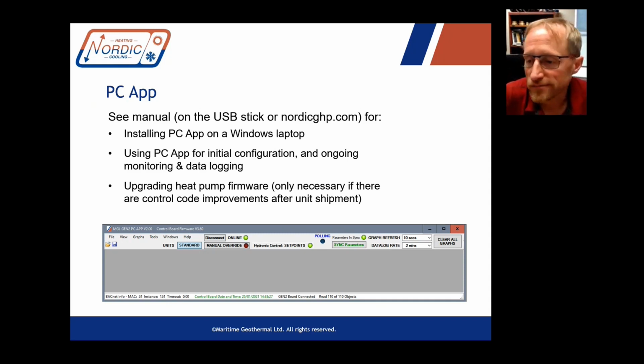Or if there's some problem with the way the heat pump is running, you can often fix it through firmware. This isn't such an issue now, but we were making quite a few improvements when these units first came out, so it was very easy for users to just upload the latest firmware and get those logical improvements, like the particulars of the way the defrost cycle worked and that sort of thing. So you can do that as well through this PC app.